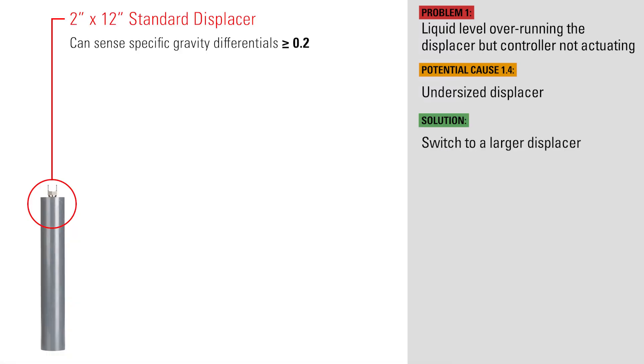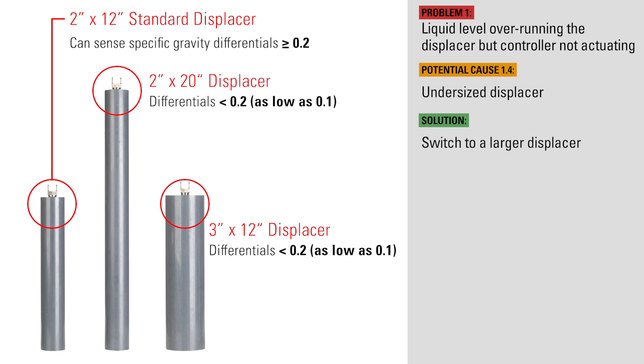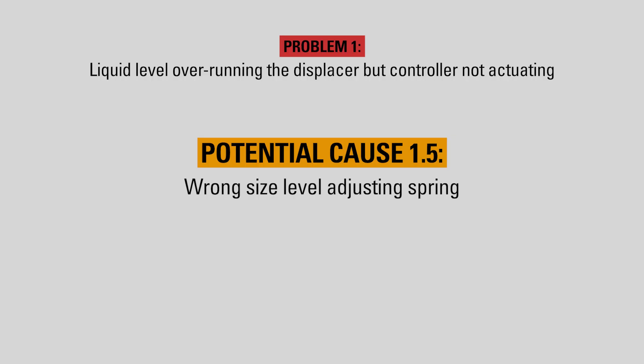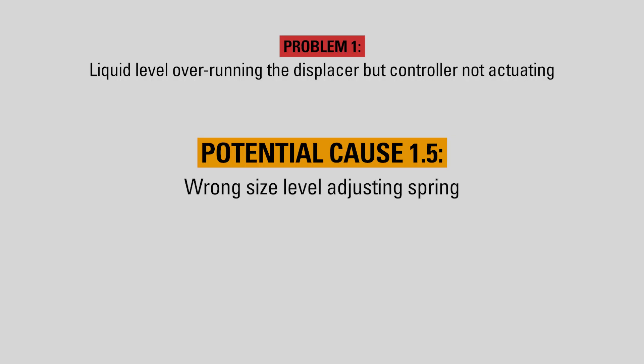Kimray's standard displacer is designed to sense specific gravity differentials as low as 0.2. If you have a lower differential, Kimray offers larger displacers that can sense down to a 0.1 differential. When switching out displacers, you may also need to change out the level adjusting spring, which brings us to our next potential cause: the wrong size level adjustment spring.